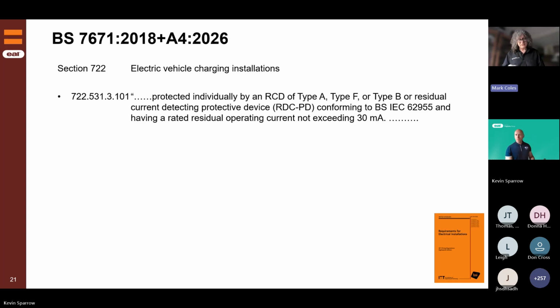So what I'm highlighting here is you can, in certain circumstances, protect the circuit to the charge point. If the charge point includes some form of RCD protection, it needs to comply with this particular regulation in terms of the RCD protection. But what's gone on this time is that where you've got DC, so you might be charging at 500 volts DC, whatever, one option now is you can use an RDC-PD in the installation. That's gone in as another method of protecting against DC fault currents.